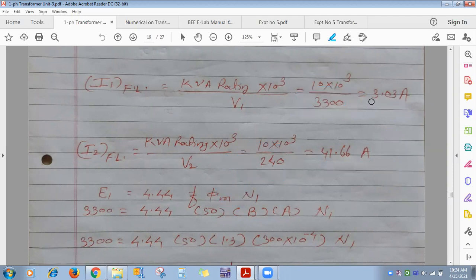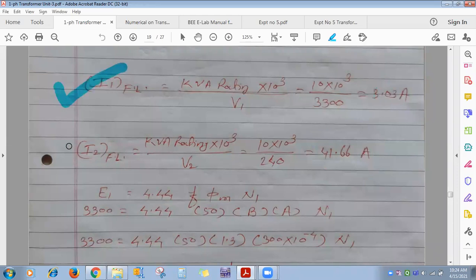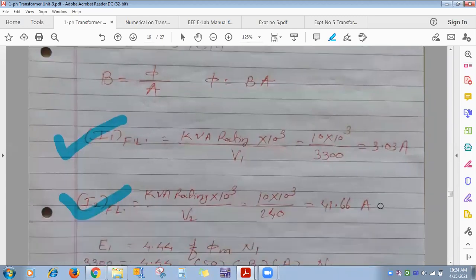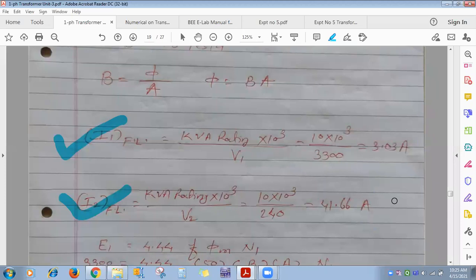The significance of these values: the primary current must not exceed 3.03 A and secondary current must not exceed 41.66 A; otherwise the transformer windings will burn. Never overload the transformer — replacement cost is very high.